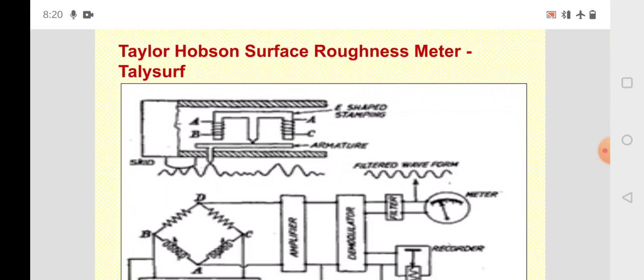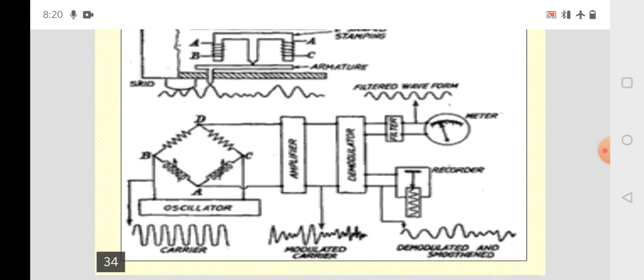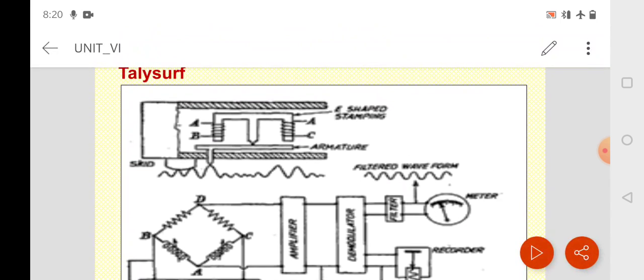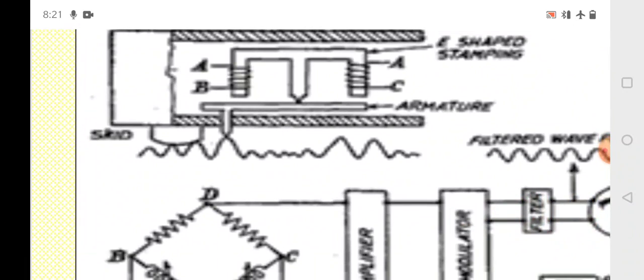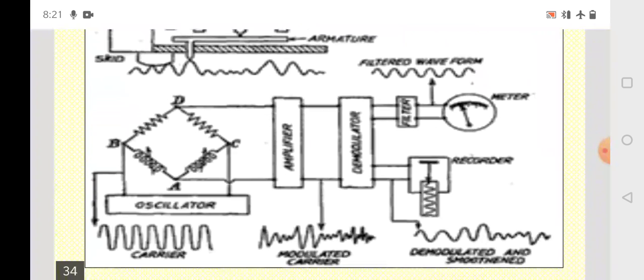Then the Taylor-Hobson surface roughness meter, that is known as Talysurf. This is an electrical type of surface roughness meter where this armature is there and this resistance; this armature is connected directly to this stylus. This stylus is moving on the roughness. See this. As this stylus moves on this surface, it will move this armature up and down. So if this armature is connected with some resistance, this bridge will get disturbed, and because of that we can get some value on the meter, and we can directly plot that reading in the form of a graph.